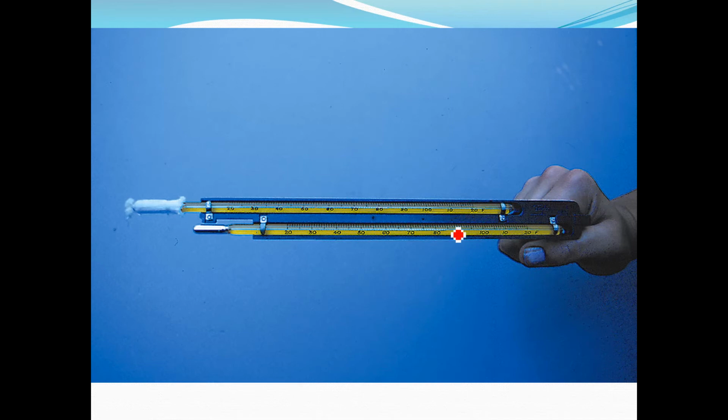Now we displace the other thermometer so that it doesn't feel those effects. This thermometer is called the dry bulb. This one here is called the wet bulb. After a few minutes, we can calculate what the wet bulb temperature is based on how much it cooled from swinging this thing around, how much it cooled from that evaporation, and we can compare it to the dry bulb temperature. Once we do that, we can determine the relative humidity using a table.